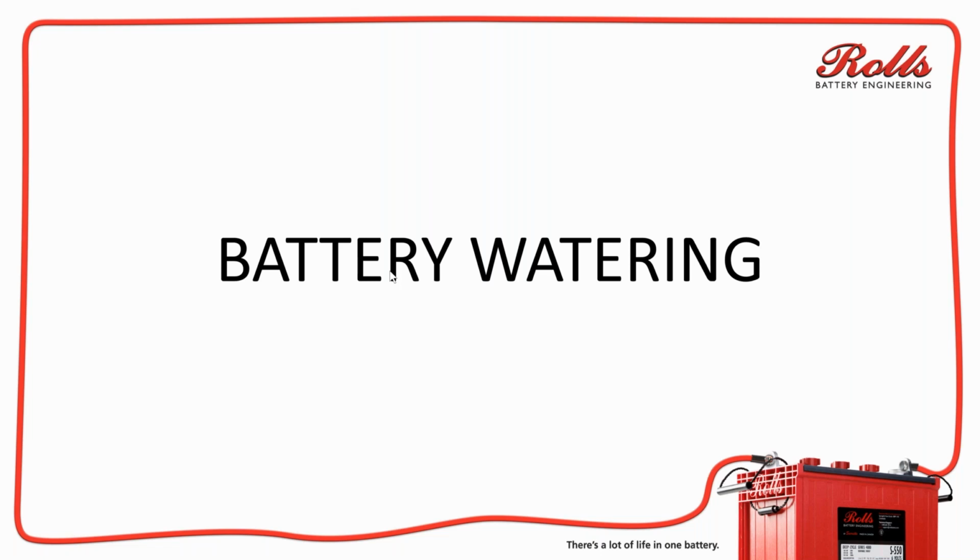As long as it's a closed loop communication, you won't have to go back through and balance those cells every 6 to 12 months. The reason for that is that with closed loop communication, the batteries control the inverters. For example, let's say you had an Outback Radian, a Schneider XW, an SMA, or a Victron inverter. Midnight is not quite there yet, but those 5 units, including the Studer, but there's not a lot of Studer stuff in North America.